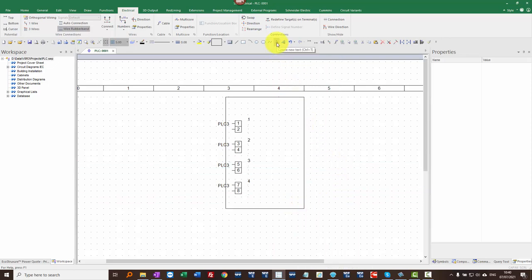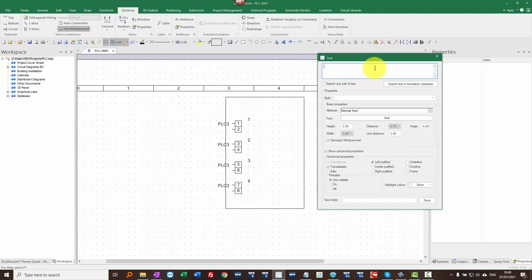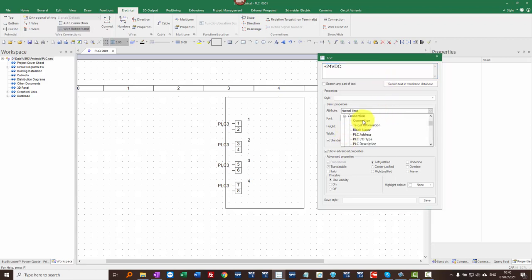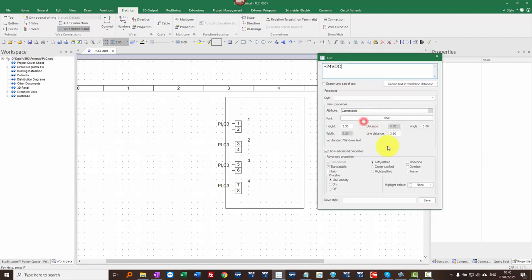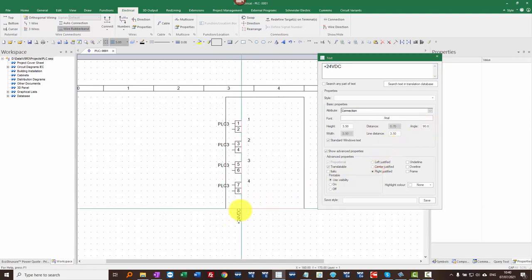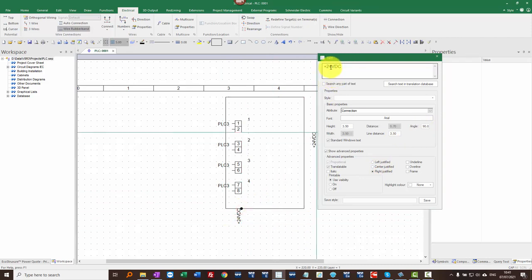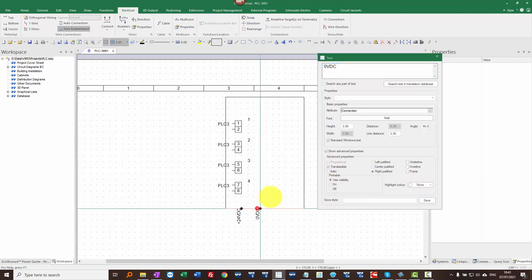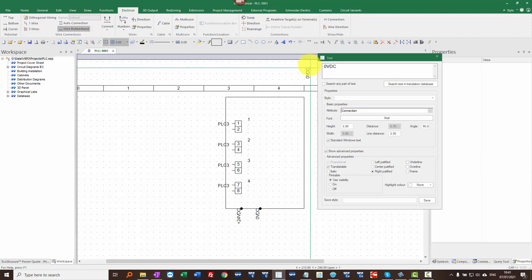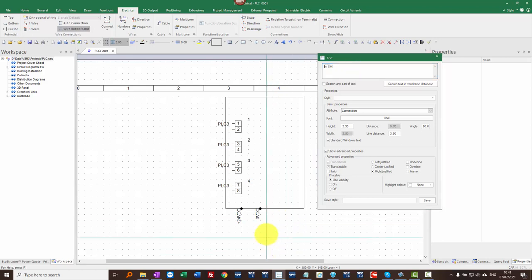I'm going to add some connection point text. I'll go to Create New Text and put +24V DC, and I'm going to set this as connection text. I go into the connection and double-click on the first attribute — so now wherever I click will be a connection point. I'm going to rotate that 90 degrees, with it right-justified, and place it there. Then I'm going to add 0V DC. I'll also add an Ethernet connection — just leave my cursor in the box and put Ethernet in there as well. So these are connection points you will be able to connect to.